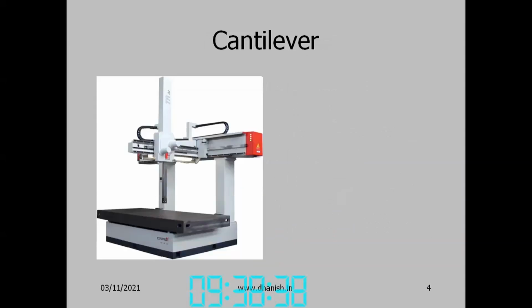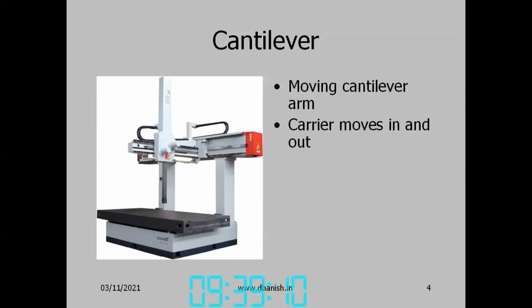Then we have the cantilever type CMM. Here the bridge is supported only at one end by another bridge. The bridge can move to the left and right, and on it the ram goes up and down, and the ram can also move forward and backward. So we have a moving cantilever ram. The carrier moves in and out. They don't have any bearing guideways, whereas in the moving bridge, the table itself acted as a guideway. So that problem is not there. Accessibility is very good, so you can access the workpiece from any point.